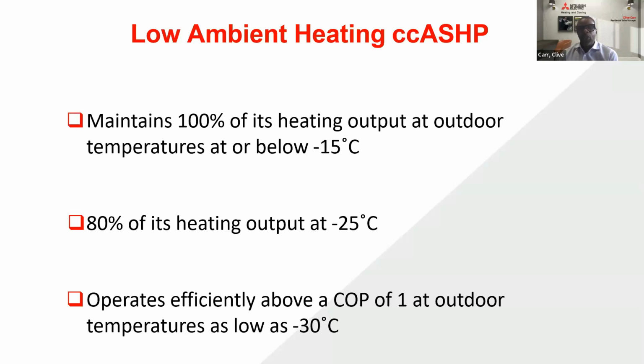Other manufacturers continue to improve on the performance of air source heat pump technology because the government is driving manufacturers to produce more energy efficient technology and systems that can help with GHG reduction. In a cold climate system, there are two test points, or reference points, used: minus 15 degrees Celsius and minus 25. Why these two points? We're traditionally used to the two points being 47 degrees Fahrenheit and 17 degrees Fahrenheit, or 8 degrees Celsius and minus 8 degrees Celsius. Those are the two test points at which the majority of heating systems are tested.